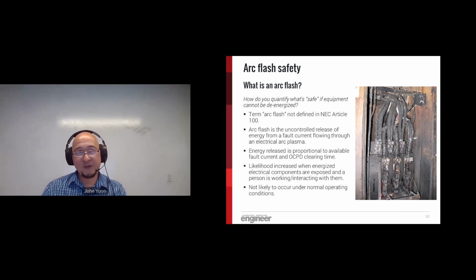All right, this is a bit backwards. We probably should have talked about exactly what an arc flash is before diving into the code requirements. So let's make this quick. Let's focus on the last 2 bullet points in this slide. Arc flashes usually don't happen spontaneously when no one is around. Normally, they are the direct result of someone interacting with the equipment. That person is typically doing something that initiates the event. It might be racking out a breaker, it could be dropping a tool, whatever.